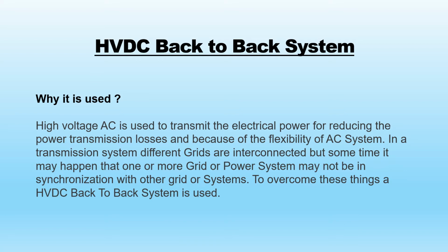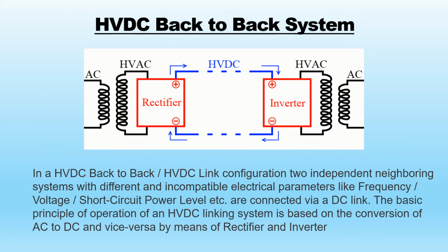In a transmission system, different grids are interconnected, but sometimes it may happen that one or more grid or power system may not be in synchronization with other grid. To overcome these things, a HVDC back-to-back system is used. In an HVDC back-to-back system, two independent neighboring systems with different and incompatible electrical parameters like frequency, voltage, short circuit power level, etc. are connected via DC link.